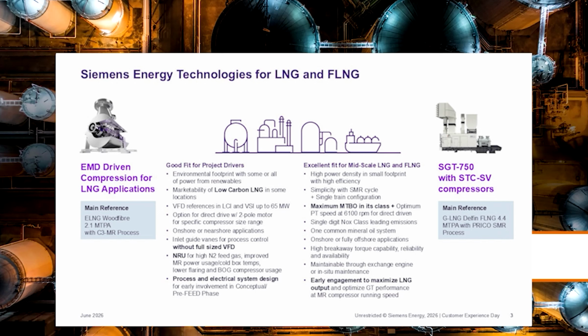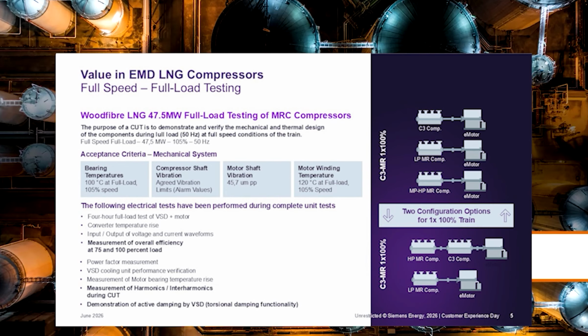The SGT-750 has the maximum mean time between overhauls in its class, and its optimized speed of 6,100 RPM fits really well with the mixed refrigerant compressor in that size, at like the 40 megawatt size for the mixed refrigerant compressor. So that allows you to do direct drive, no gearbox, cutting out that additional amount of loss in the efficiency of the drivetrain. So this was an excellent project. We'll talk a little bit more about that in the coming slides.